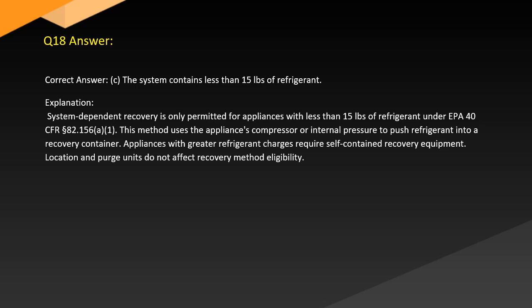Answer. Correct answer, C. The system contains less than 15 pounds of refrigerant. Explanation. System-dependent recovery is only permitted for appliances with less than 15 pounds of refrigerant under EPA 40 CFR Part 82.156, A1. This method uses the appliance's compressor or internal pressure to push refrigerant into the recovery container. Appliances with greater refrigerant charges require self-contained recovery equipment. Location and purge units do not affect recovery method eligibility.